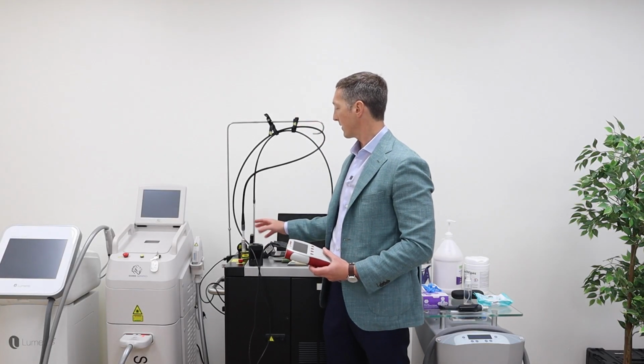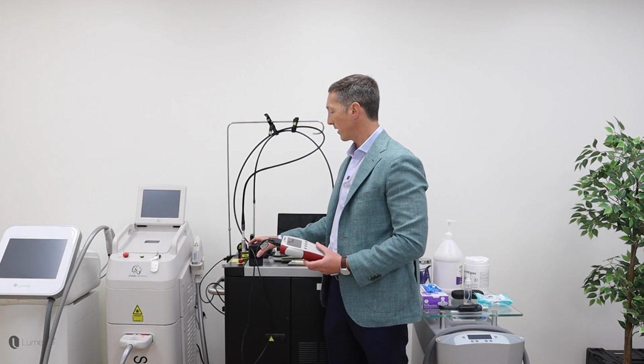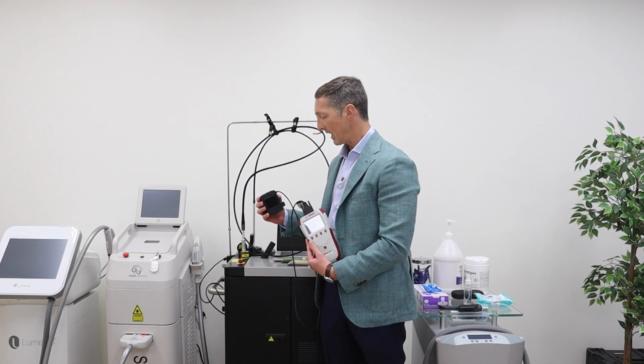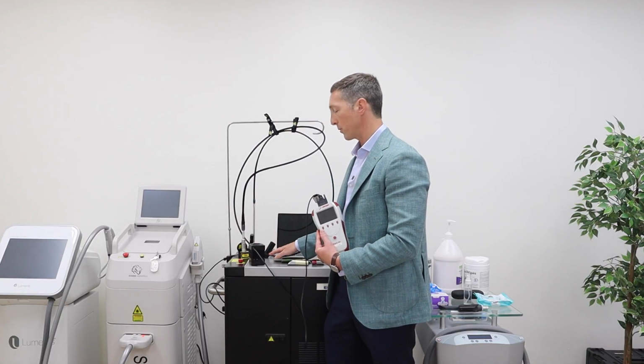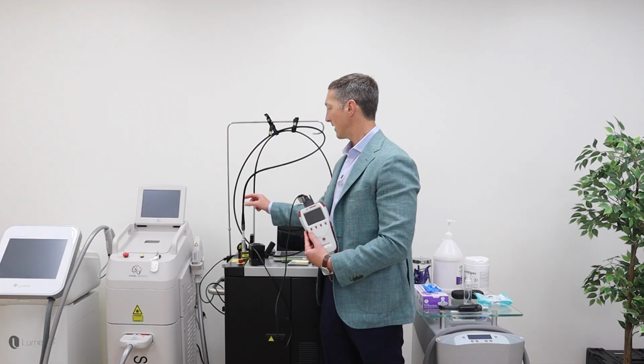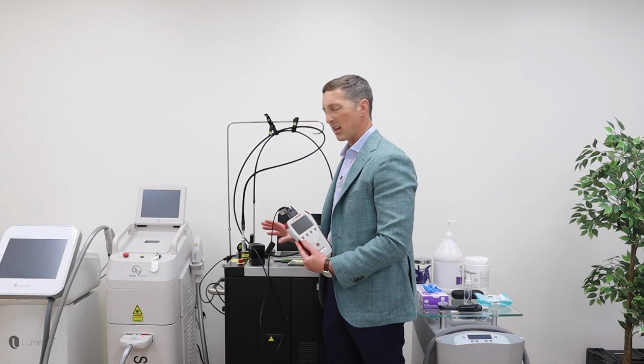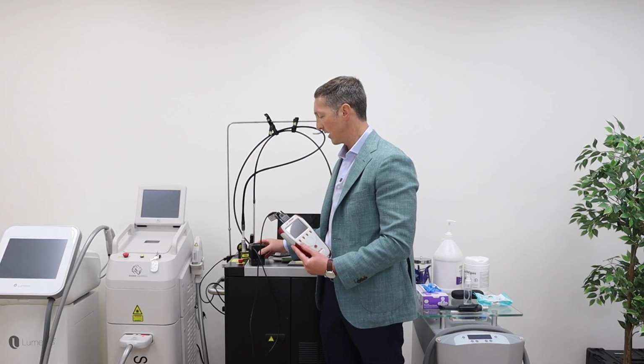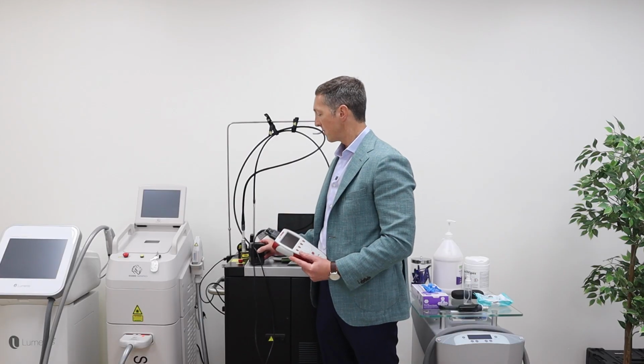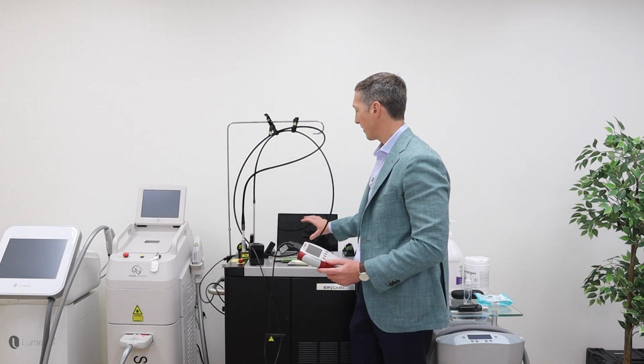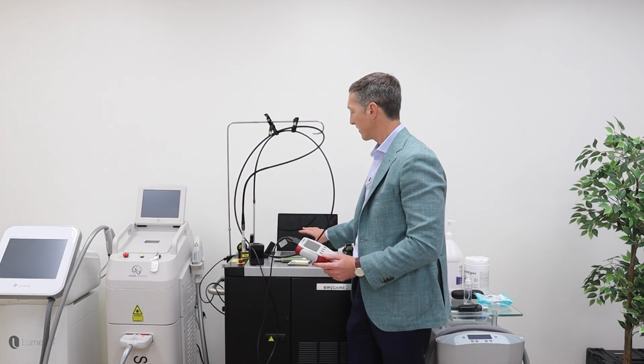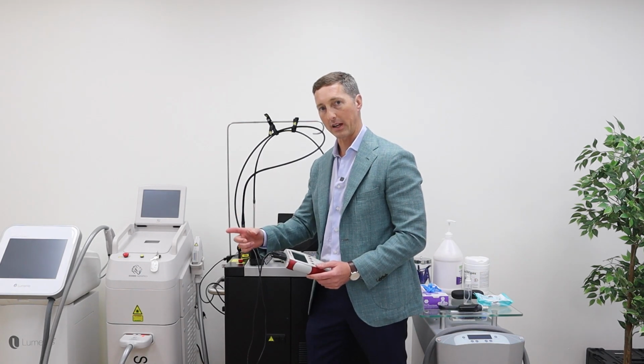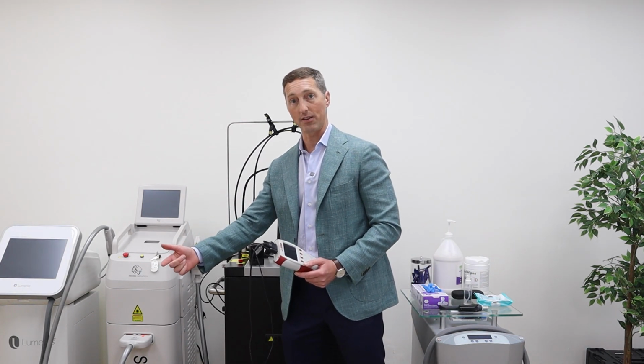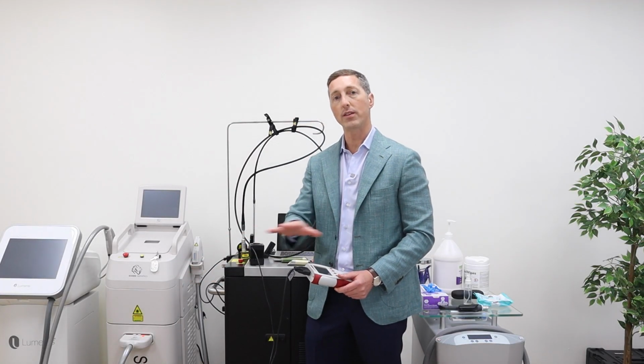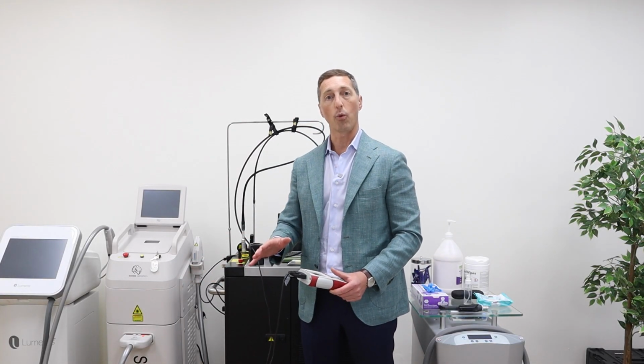So what you end up doing is we will test the output of the laser system against this external meter. And then we will make the proper adjustments with our software system, ensuring that this is more or less plus or minus just a few percentage of what this is saying that you have. And so we're making sure that the verification is correct and that this system is actually putting out the energy that we think it's putting out. And then we're going to do the same thing on your next laser system and then your next laser system. And that's the only way to ensure that all systems within your clinic are actually uniform.